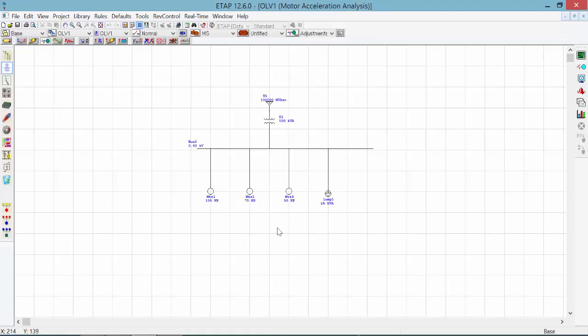Inside ETAP acceleration analysis, we can run two types of motor starting analysis. The first one would be static motor starting, and the second one is called dynamic motor starting. With the static motor starting, ETAP calculates the impact of the load being connected to the line directly and would give us some useful information such as the voltage of the load at its terminal, the real and reactive power of the load, and also the voltage dip level at the bus which the load is connected to.